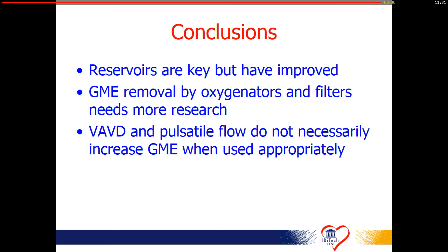That's the reason why they introduced screen filters, because a screen filter is not vulnerable to that. But a screen filter is less performant in actually removing GME. And this was known from the early days, because there are very old articles already showing that a depth filter, which existed at the time as an arterial filter, was the best performing one in removing all air. But why did they stop? Because it also took all the platelets out of the blood. So again, the story comes back. The best safety is not hemocompatible, and vice versa. We need to find the in-between, which is acceptable for both arguments.